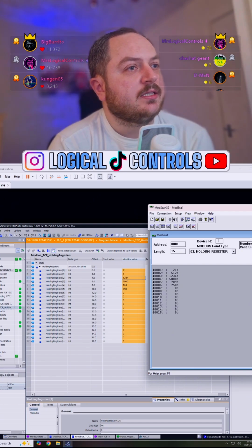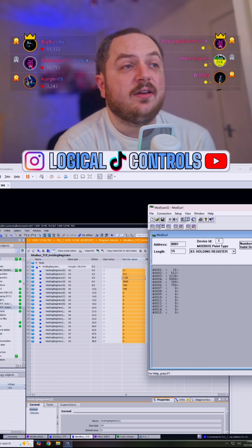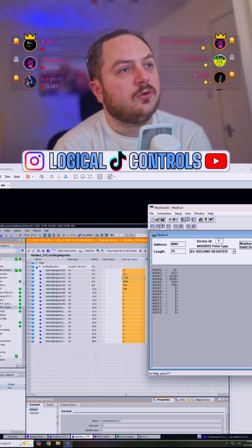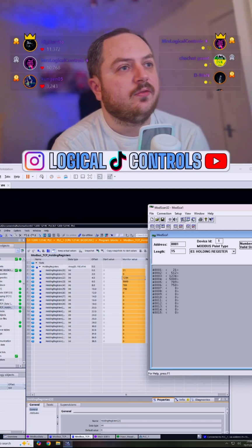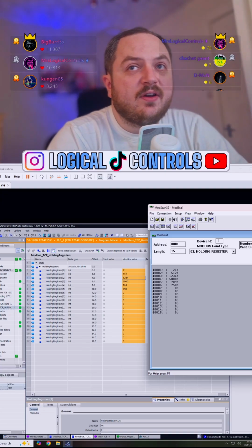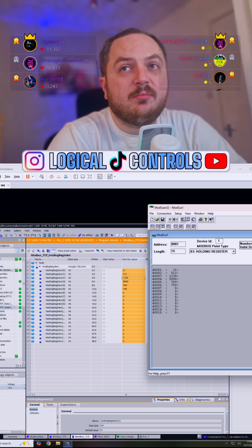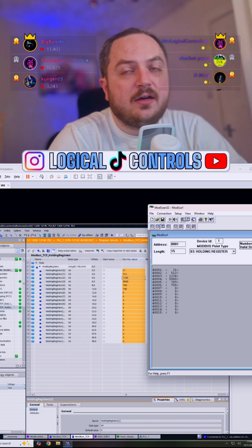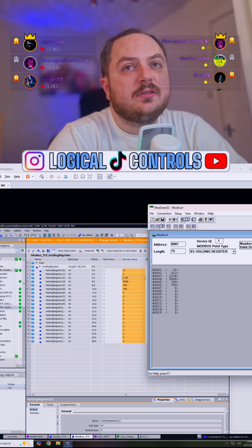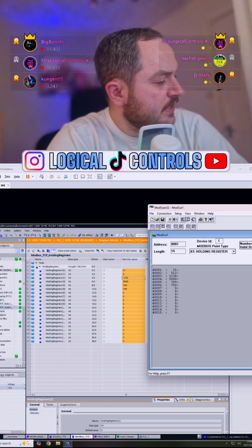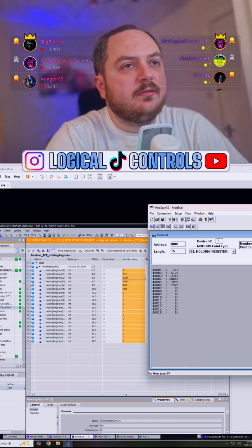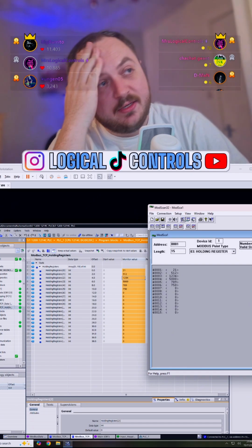Slow speeds sounds like LonWorks. I never used LonWorks either. I'm aware of it because old Cummins controllers used LonWorks, but they had a converter for Modbus. Yeah. The thing with Modbus is it's very open. It's very easy to use, but it is slow. It's not like EtherCAT or any of these newer protocols these days. CC-Link IE TSN, is it, or something like that? It's like real time or something. Yeah, I don't really use it.